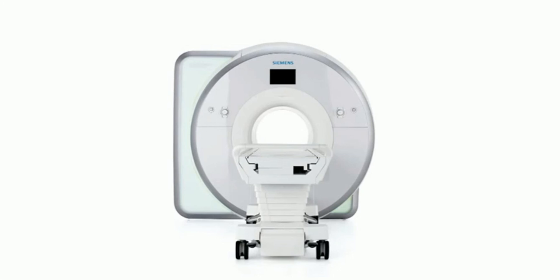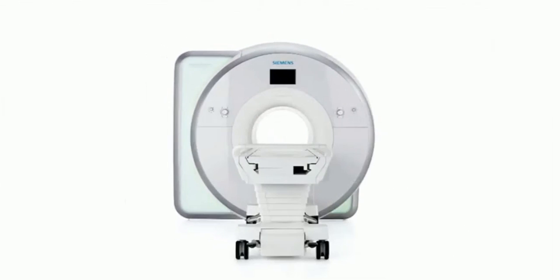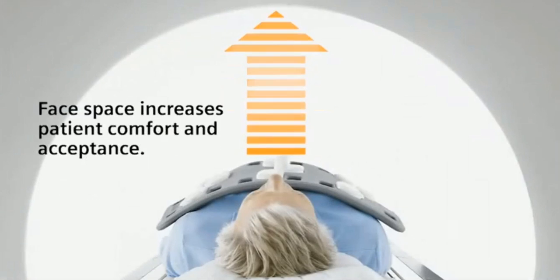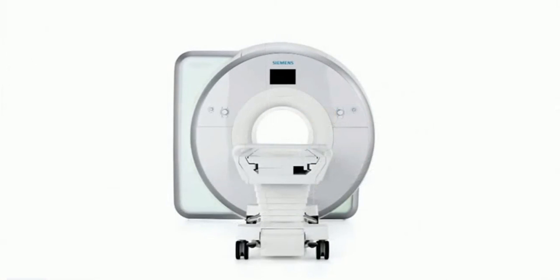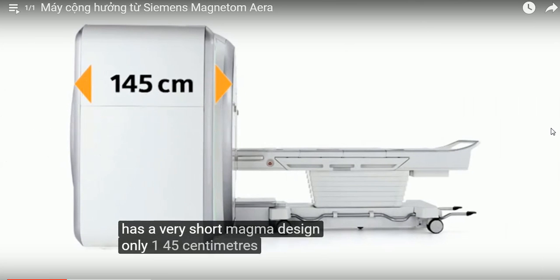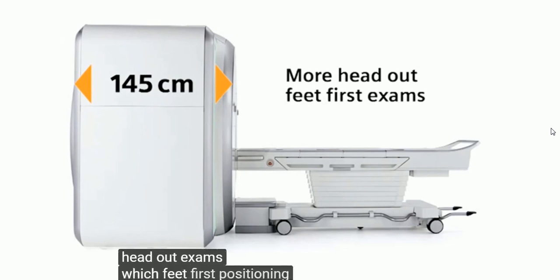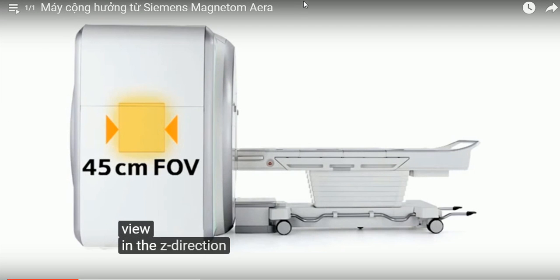The Magnetom AERA continues with Siemens' open-bore design, keeping the established benefits of the 70 cm bore, including increased face space and accommodation of larger patients and patients with special needs. The 1.5 Tesla Magnetom AERA has a very short magnet design, only 145 cm cover-to-cover, which allows more head-out exams with feet-first positioning.